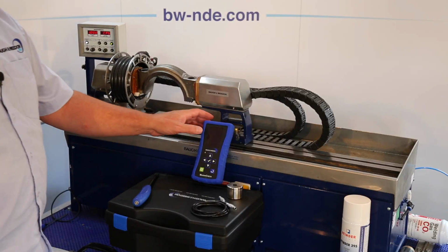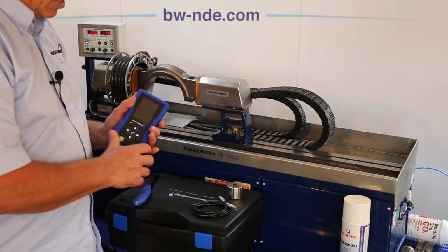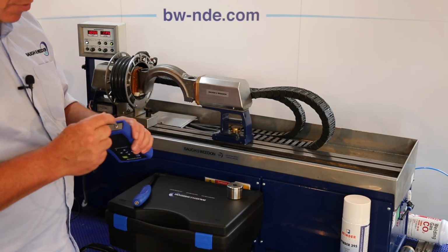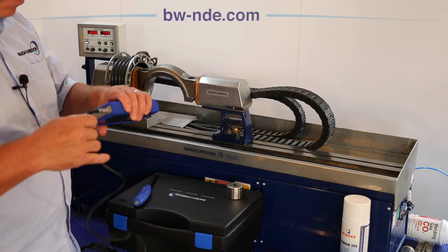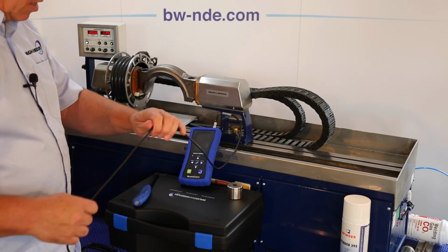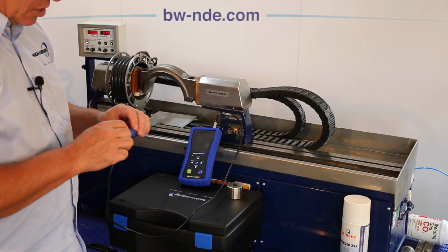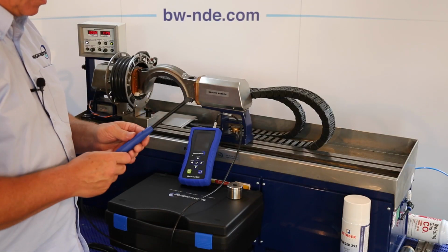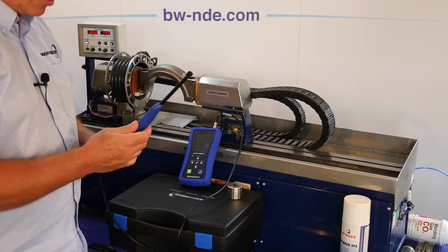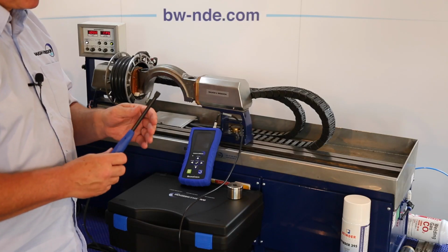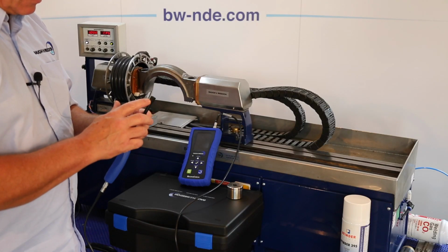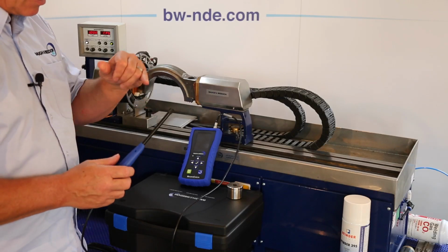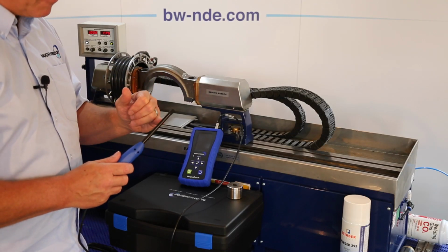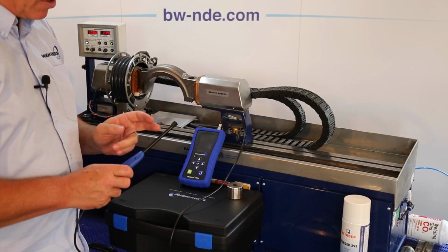Let's have a look at the MagnaCheck 3D in some more detail. To connect the unit up, line up the two red dots. Then connect the probe lead to the probe in the same way. The probe lead is unique and designed and manufactured by Baugh and Weedon. It has different letters on each face, so you can measure an average or you can measure in two directions.